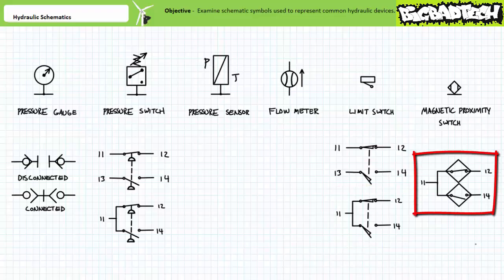Here's the electrical schematic symbol for a magnetic proximity switch, making use of a single-pole double-throw transfer contact with both a normally closed and normally open side being serviced by a single common terminal. Single-pole double-throw transfer contacts are very common for solid-state devices. Note magnetic proximity switches necessitate additional power connections not explicitly illustrated in the electrical schematic. These power connections power the solid-state detection mechanism necessary for proper operation.